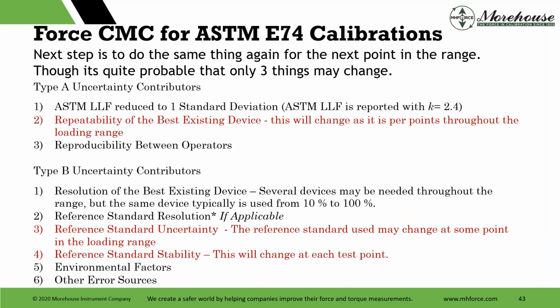So you keep doing the same thing again. Next step is do the same thing again for the next point in the range. You start doing this, it gets pretty easy. Only 3 things that typically change with the E74 cal: repeatability of the best existing device, reference standard uncertainty is probably going to change, and the stability will change.